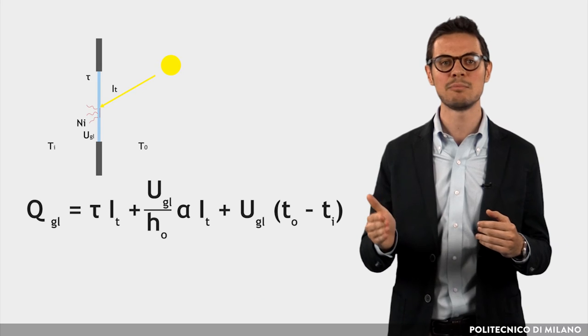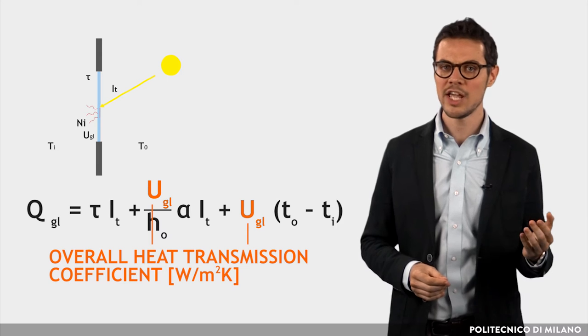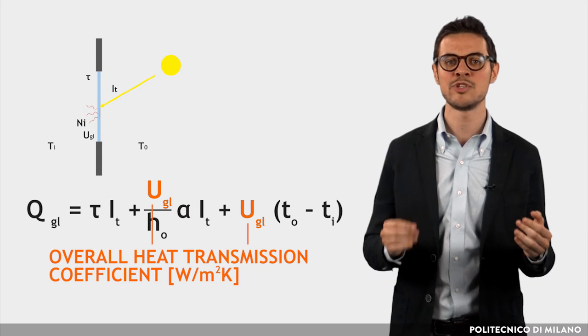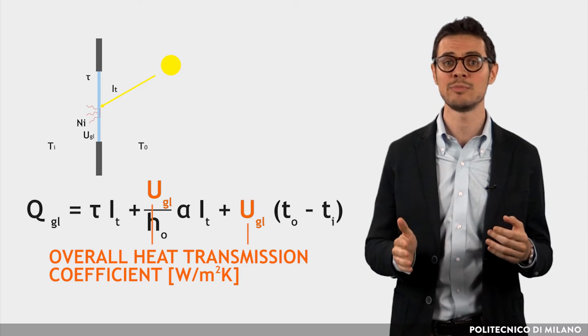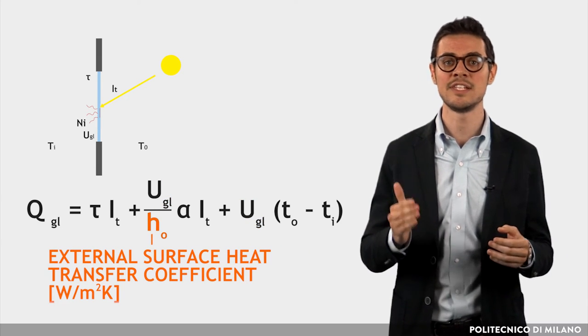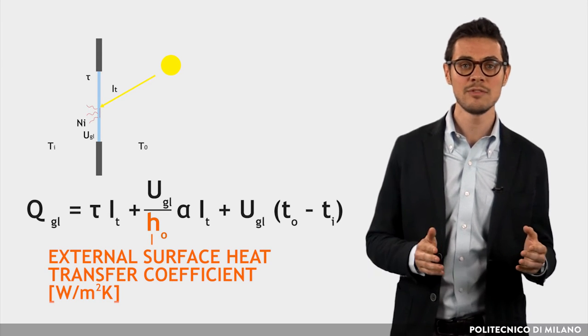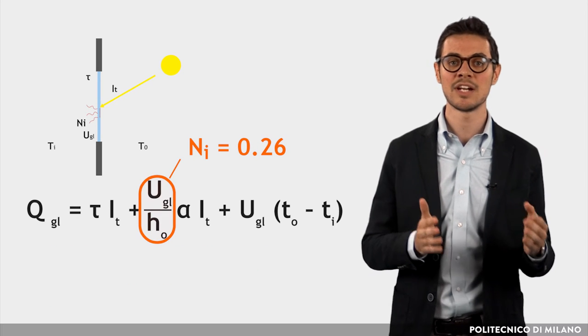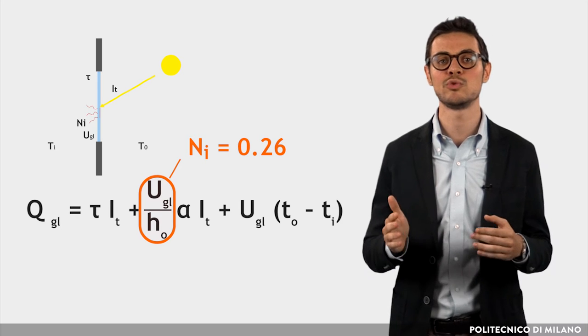Given by the ratio U_GL over H_O, where U_GL is the overall heat transmission coefficient of the glass, expressed in Watt over square meter Kelvin, and H_O is the external surface heat transfer coefficient in Watt over square meter Kelvin. Generally, for a 3 mm clear glass, N_I can be considered a constant and equal to 0.26.